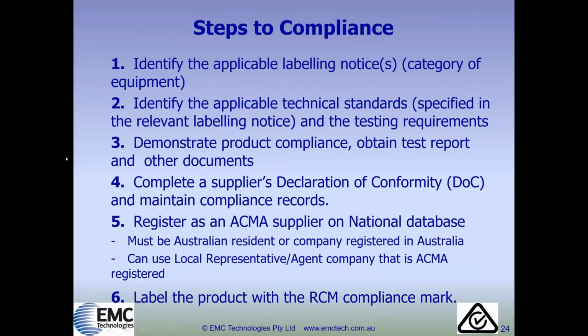Well, first of all, you identify the applicable labelling notices that apply to your product. You identify the technical standards that the labelling notice calls up. In the case of EMC, it'll be EMC standards. In the case of radio, it'll be radio standards. In the case of telecoms, it'll be telecommunications standards. Identify all the standards that apply to your product. Then demonstrate compliance. In general, it's by testing in a lab, although other options are available, such as the old TCF route, which is still acceptable in Australia, by a competent body TCF route.